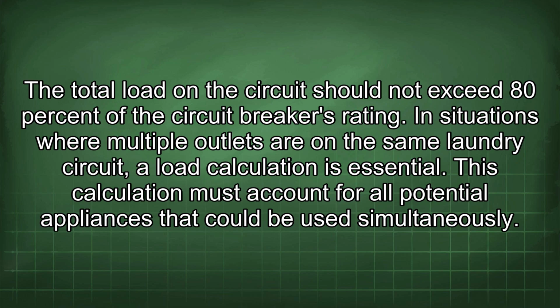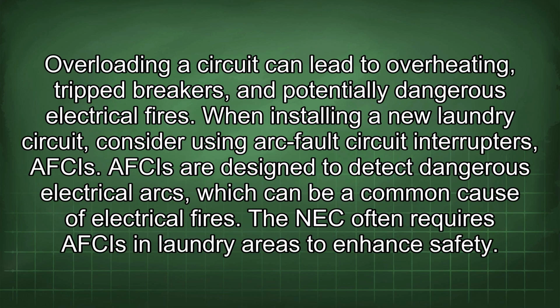In situations where multiple outlets are on the same laundry circuit, a load calculation is essential. This calculation must account for all potential appliances that could be used simultaneously. Overloading a circuit can lead to overheating, tripped breakers, and potentially dangerous electrical fires. When installing a new laundry circuit, consider using arc fault circuit interrupters (AFCIs). AFCIs are designed to detect dangerous electrical arcs, which can be a common cause of electrical fires. The NEC often requires AFCIs in laundry areas to enhance safety.